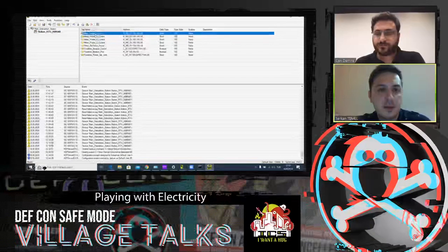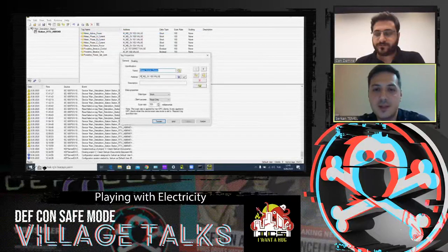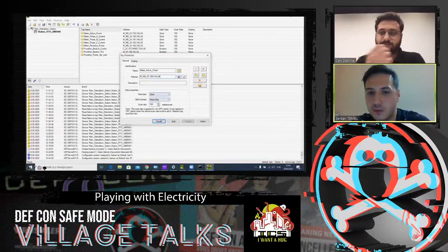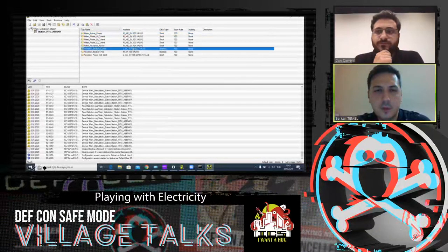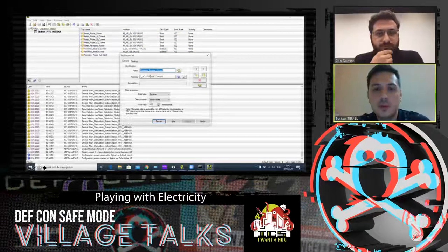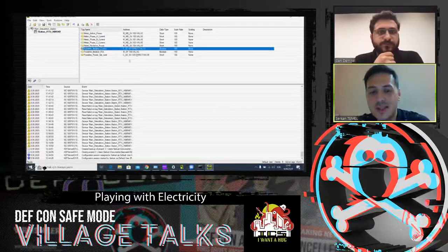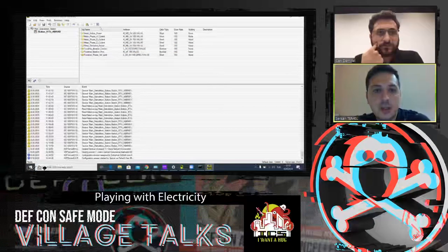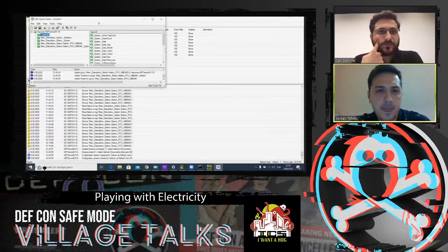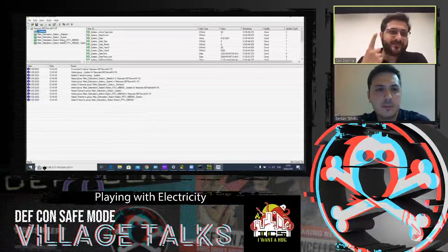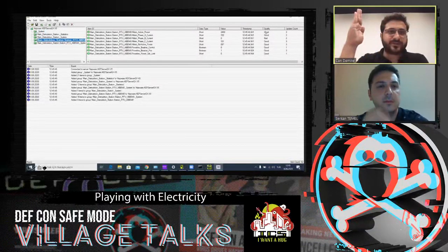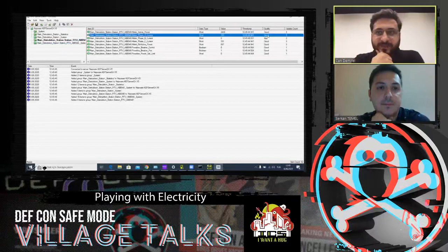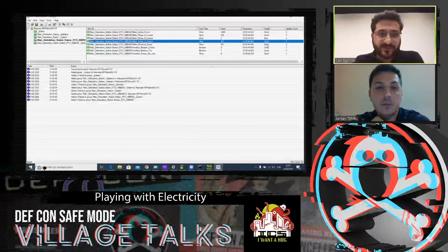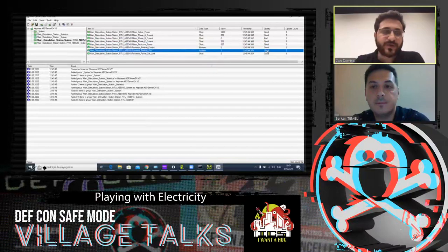And on this side, we also configure our signal. This means that it is an analog short float value. Address 1/3. And this is the breaker control command. Single command. Actually, it will directly affect opening and closing the breakers, and later we will apply some scenarios. It's really important to understand what type of parameters and what type of commands they take.